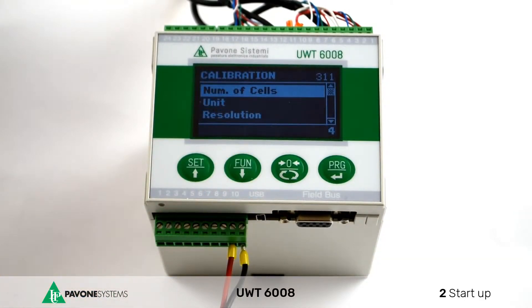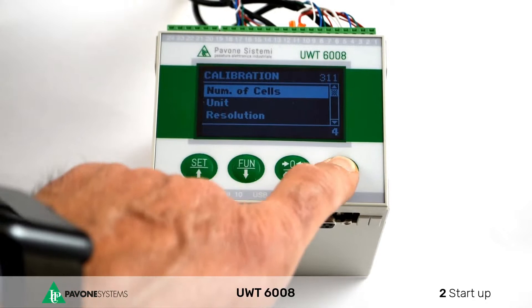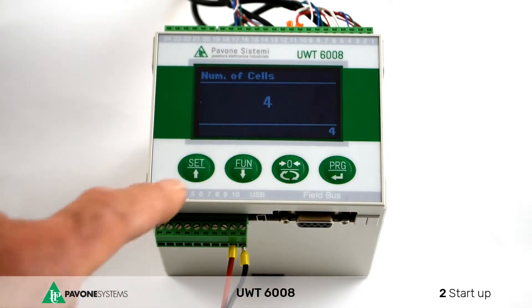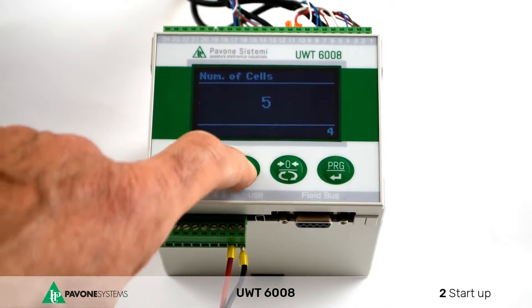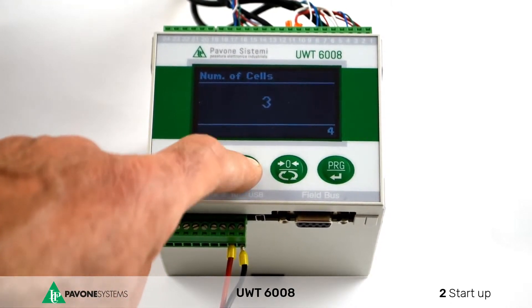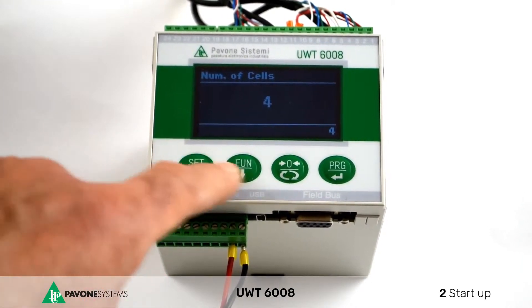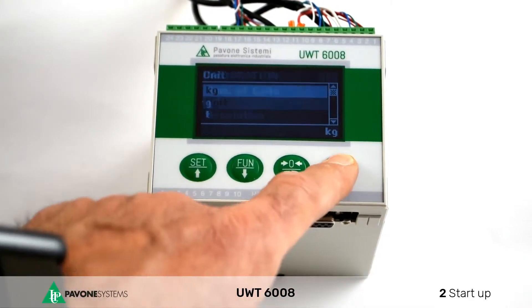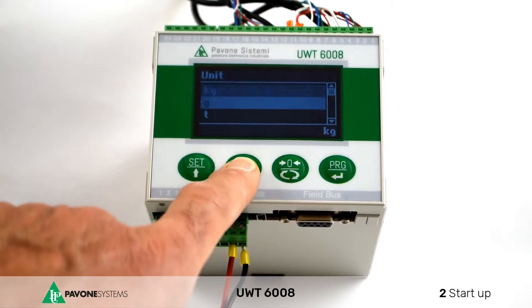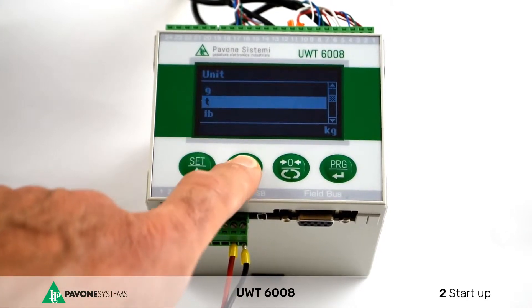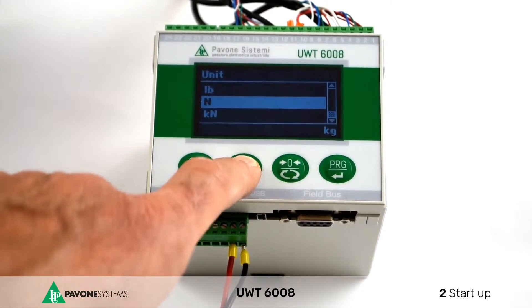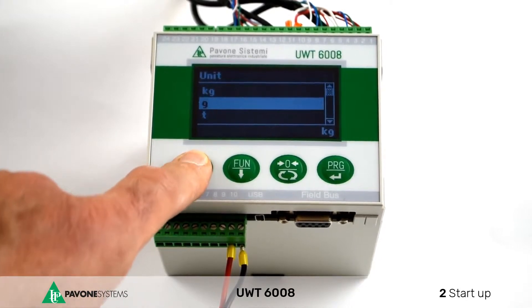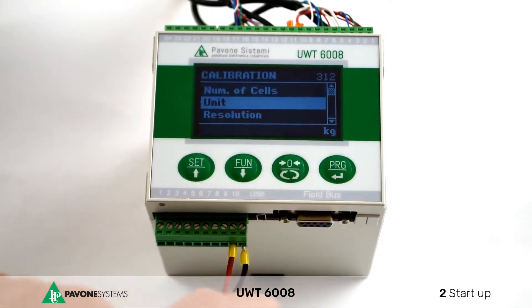Let's go on with the simulation. Insert the load cells number — in this example, 4. You can change this number by pressing arrow up or arrow down and confirm with PRG. Now choose the measurement unit, which can be expressed in kilograms, grams, pounds, tons, newton, or kilonewton. In this case the weight unit will be kilograms.